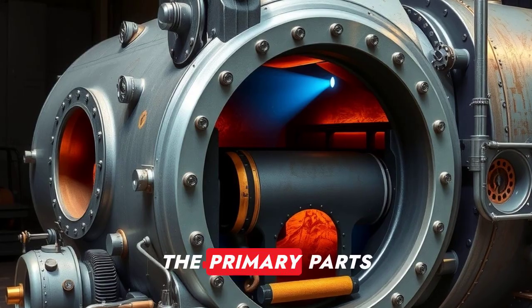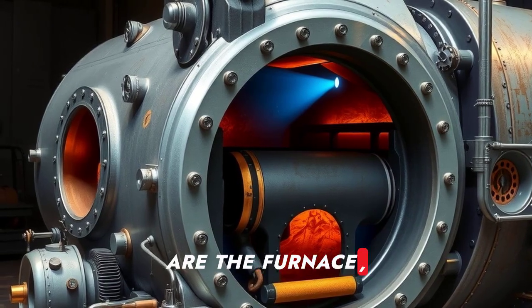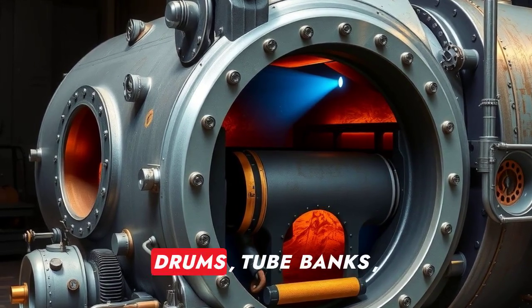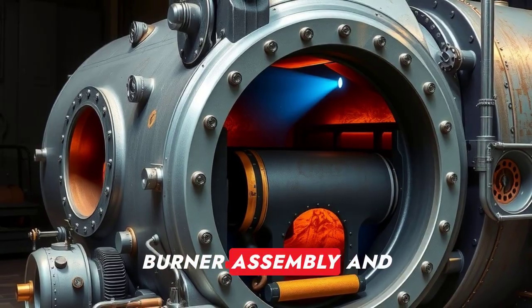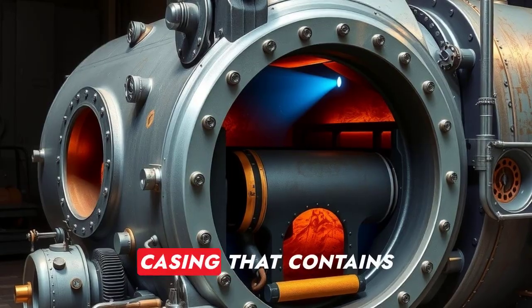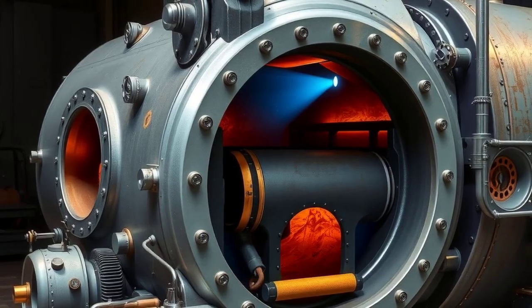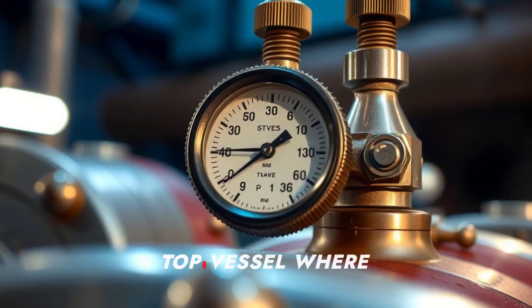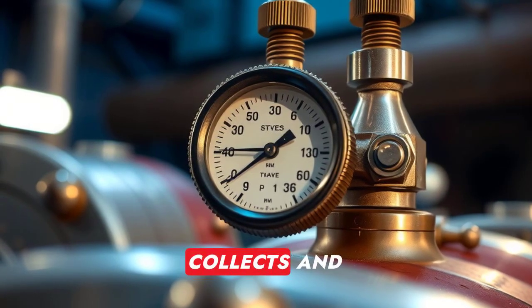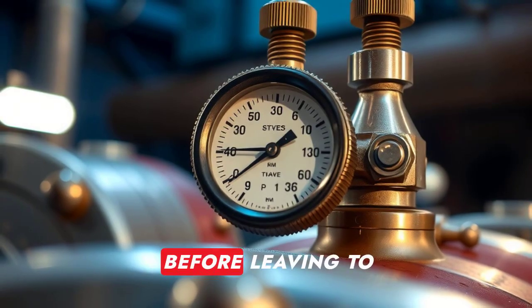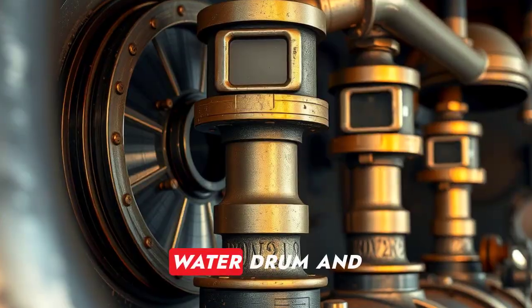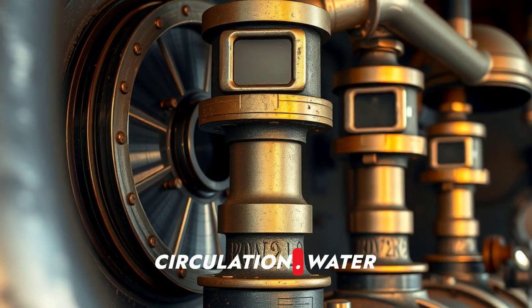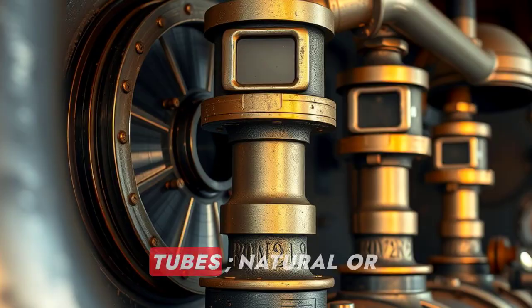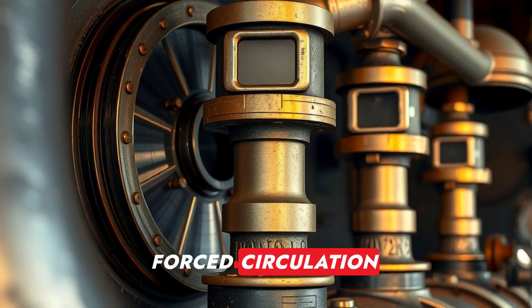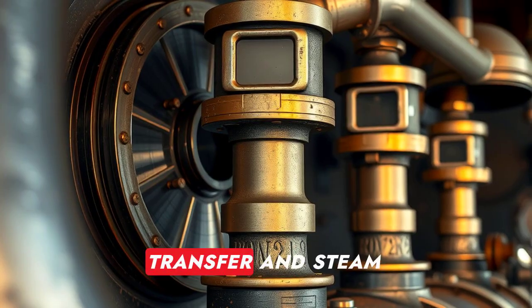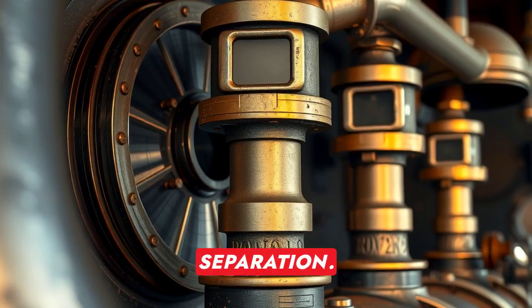The primary parts are the furnace, water and steam drums, tube banks, burner assembly, and outer shell or casing that contains the furnace. Steam drum. The top vessel where generated steam collects and separates from water before leaving to the steam header. Water drum and circulation. Water collects and circulates through tubes. Natural or forced circulation maintains heat transfer and steam separation.